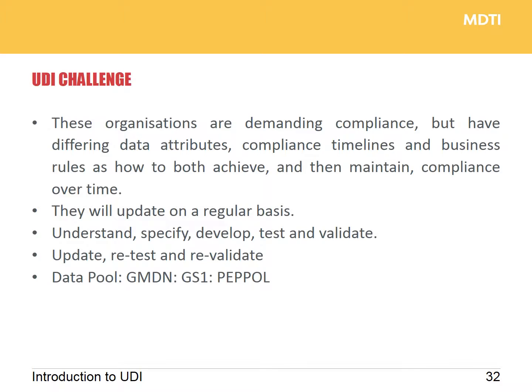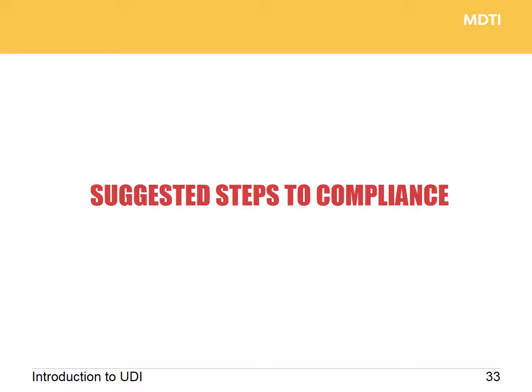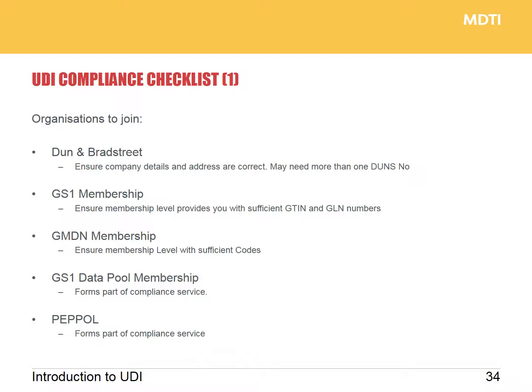It is a huge challenge. Having helped many companies go through UDI compliance, I'd like to cover some suggested brief steps you should be looking at as you start your UDI compliance projects over the coming weeks and months. The first things to do for compliance is to join the relevant organizations: Dun & Bradstreet for DUNS numbers, GS1 for your codes, GMDN for product codes, datapool membership, and also PEPPOL — we're a PEPPOL access point. You won't actually have to do anything with PEPPOL for the next two to three months, but join the organizations first and get that information into your systems.